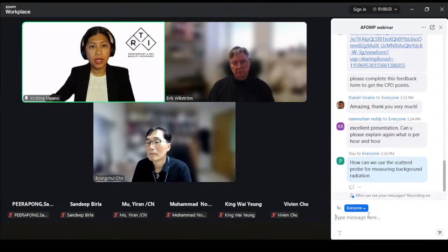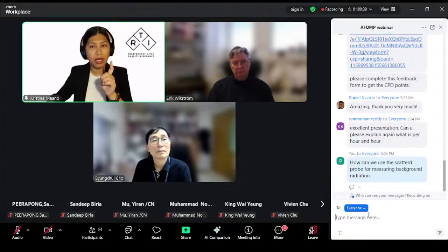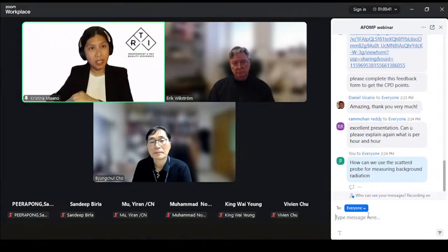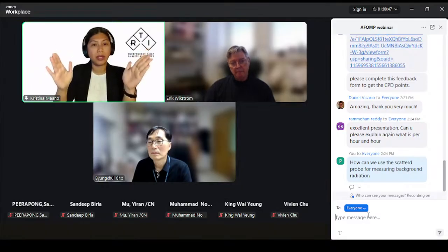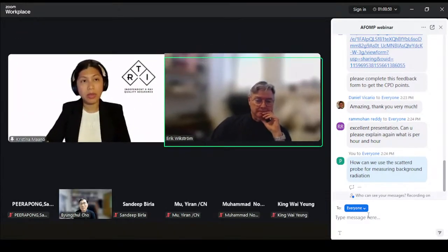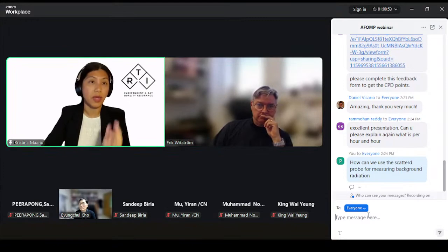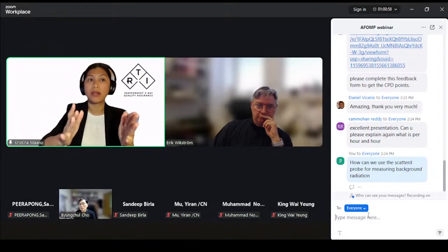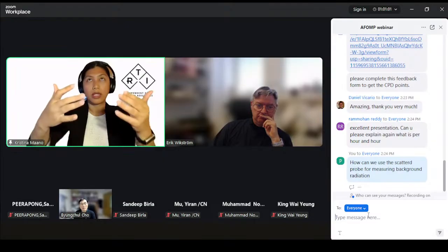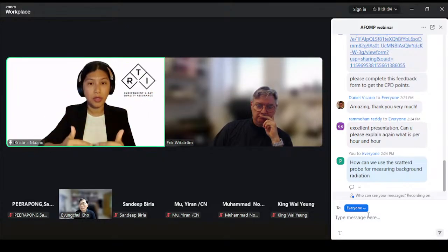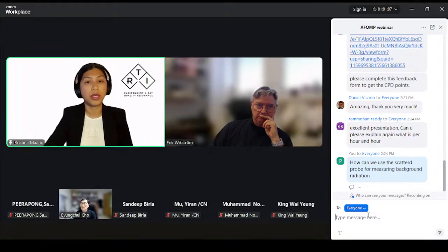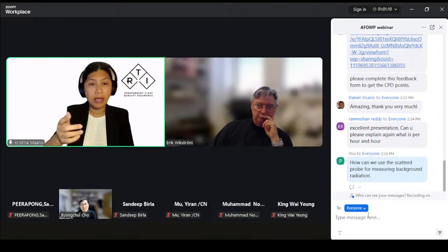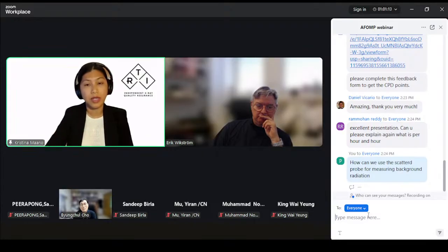It also accounts for the total workload of the machine. If we just say per hour, it's an instantaneous measurement of the dose. That's why, when we do the calculations, we account for how many hours a staff member might be working, for example, inside the room or in the control console room, and then we account for the workload. Is the staff working for 8 hours or only maybe 6 hours?